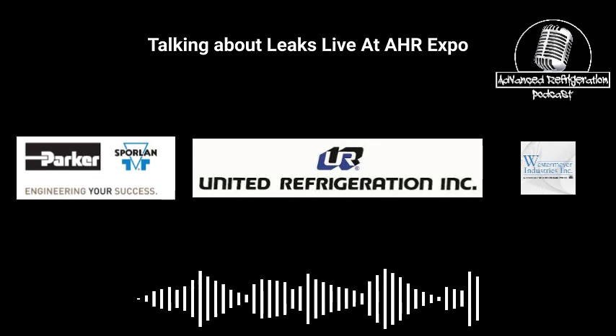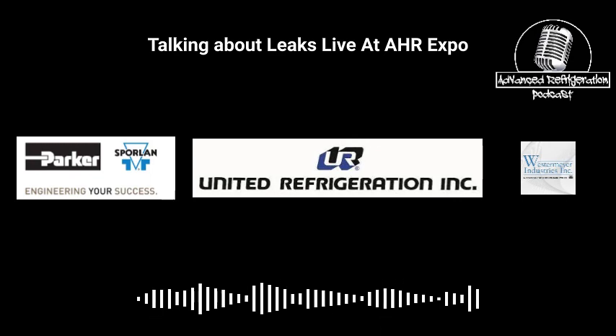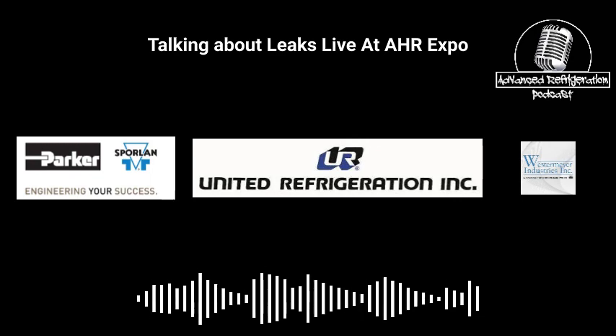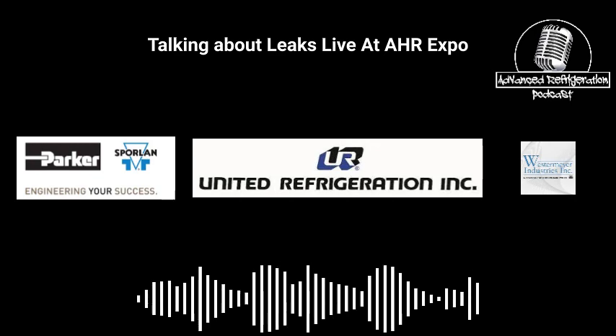Well, I leak checked this. I mean, it was an inner wall. Like I leak checked this line going in here like 4 different times myself, and like 3 other people did too, and none of us got a hit. Gotcha. Ended up being because the building was so saturated, and it just so happened that the leak detector inside the building was bad.